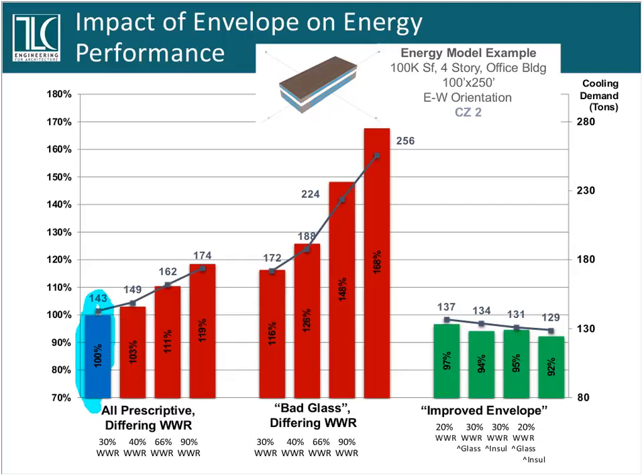The second set of graphs that I ran are what we call the bad glass. This is glass chosen by an architect who said, you know, I really love the way that glass that I saw in that building in Vladivostok looked, so I'm going to pick that glass to put on my building. If you follow everything else in the code, 30% window-to-wall ratio, all of the other code requirements, and you just put that bad Vladivostok glass on there, you're already 16% over the annual energy use allowed by the code, plus almost, once again, 30 more tons of air conditioning.